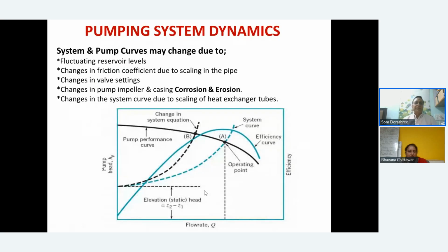Now, pumping system dynamics. In a pumping system, actually in any industry, it will be very dynamic in nature, because the reservoir level will be fluctuating, your process requirement will be fluctuating, and there will be changes in valve settings. The control valve may be based on temperature or levels or whatever is required. So this is a very dynamic system. There can also be changes in the pump impeller and casing, because even the impeller, supposing cavitation happened some time in the night shift, may then have got damaged.